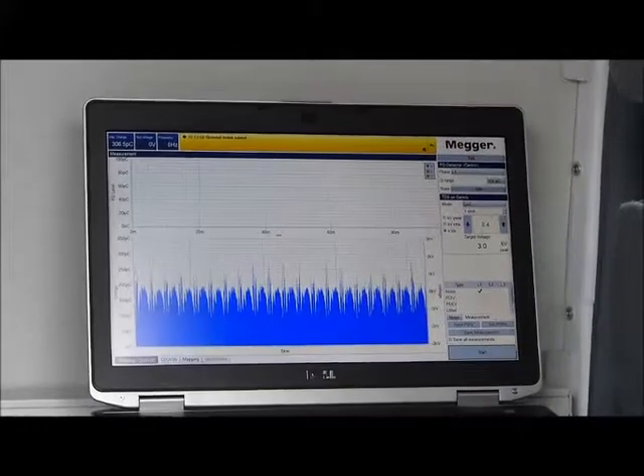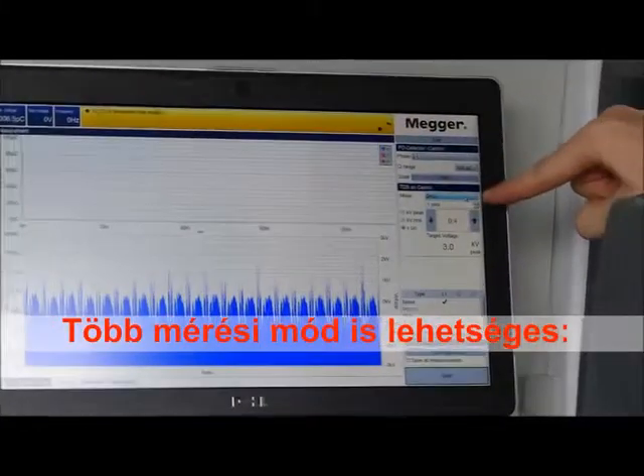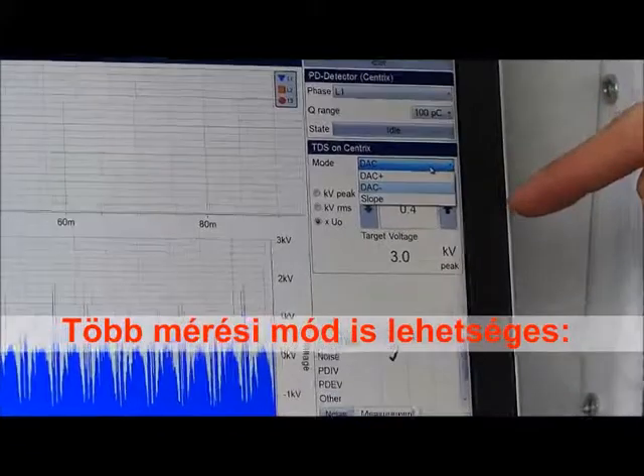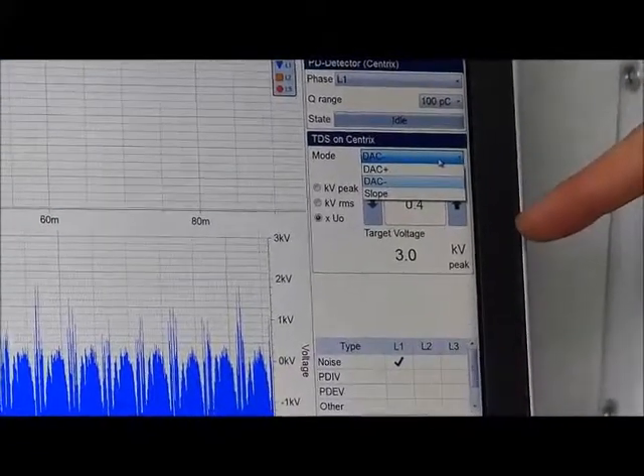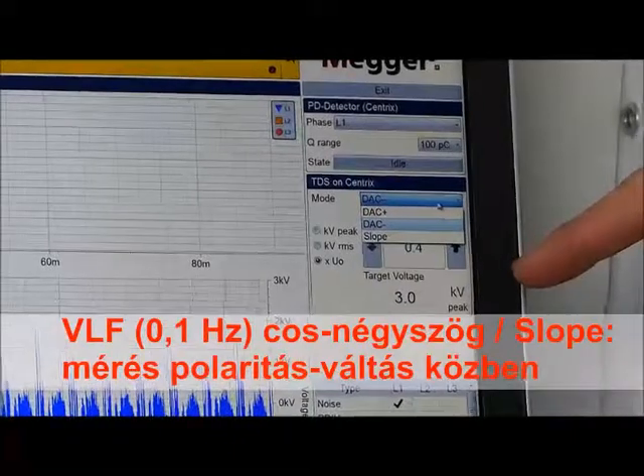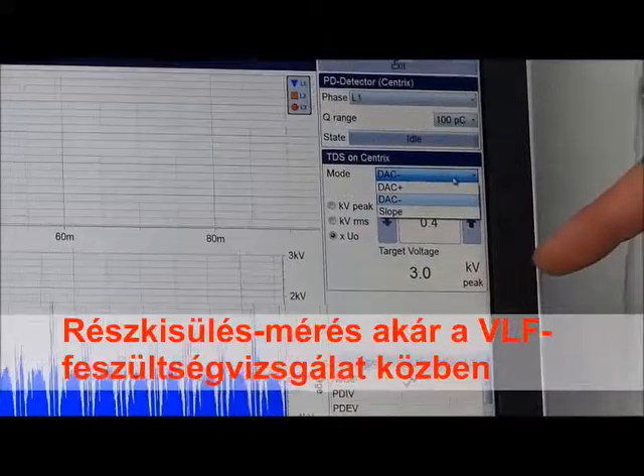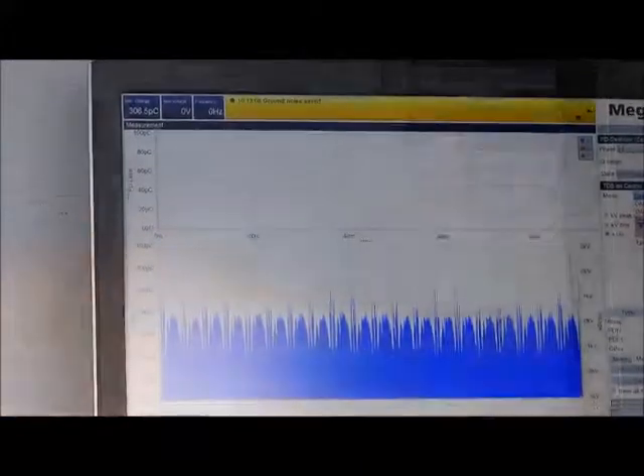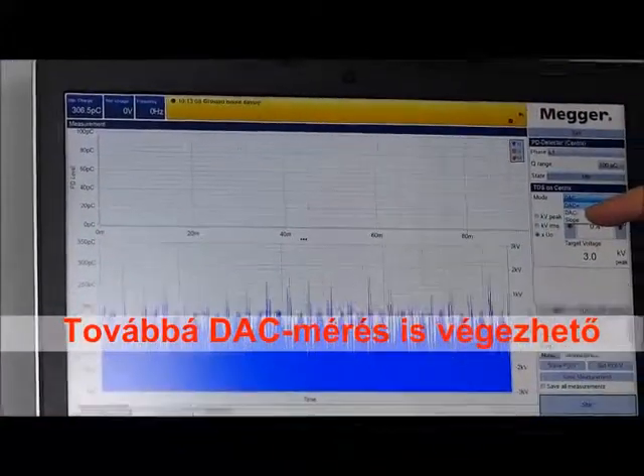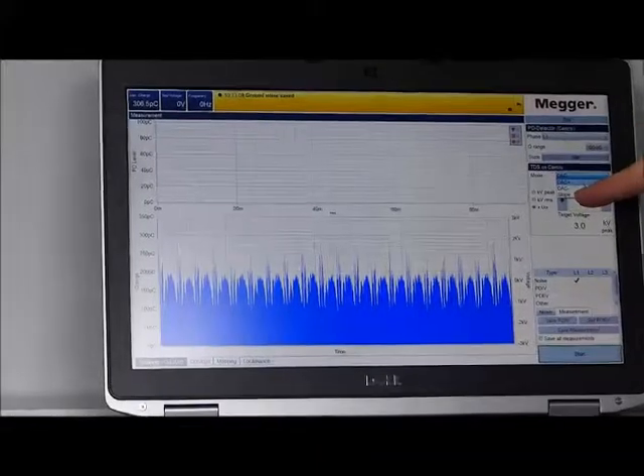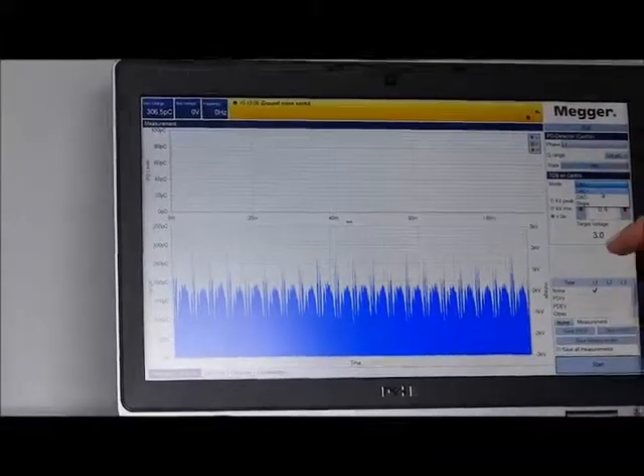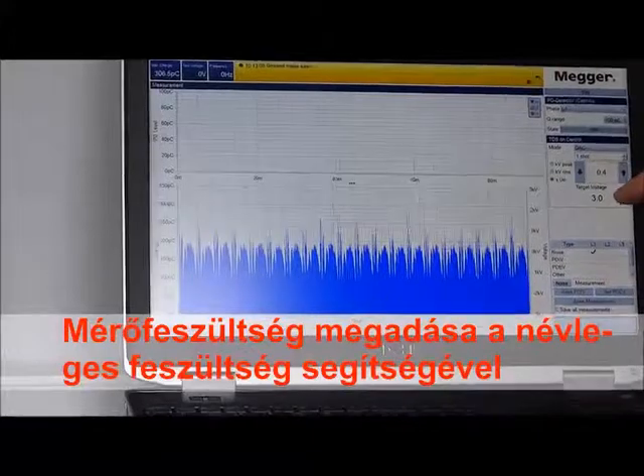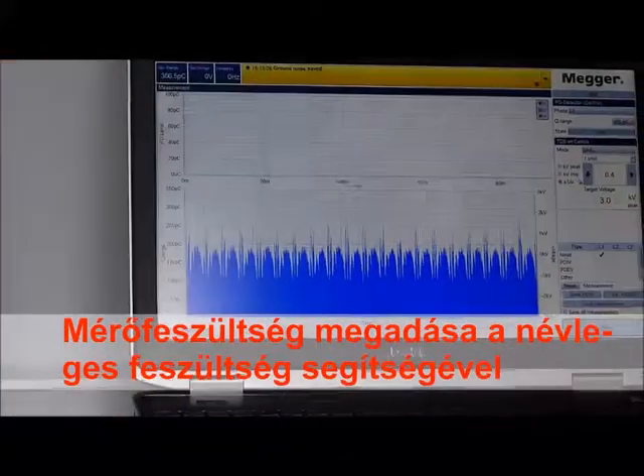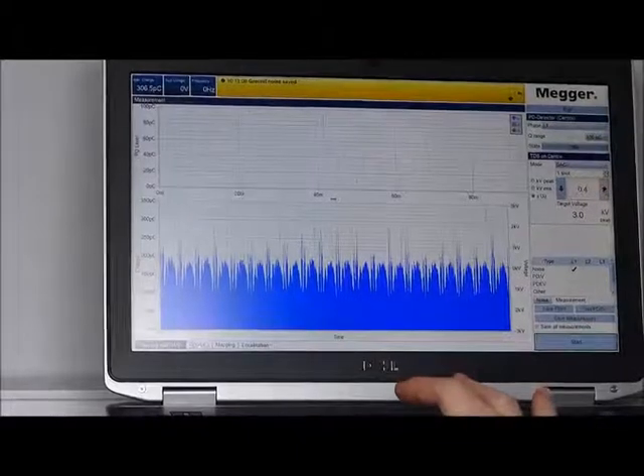And here with the system you see we are able to have several voltage sources. We have a unit with two systems. We have the VLF cosine rectangular, so you can do the VLF testing, and during that test we are able to measure in the phase reversal, we measure partial discharges. And we are able to do the damped AC measurement according to what the OWTS is doing. Like with the OWTS, we want to measure with the factors of the nominal voltage.